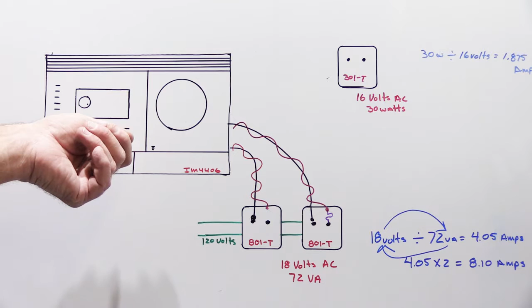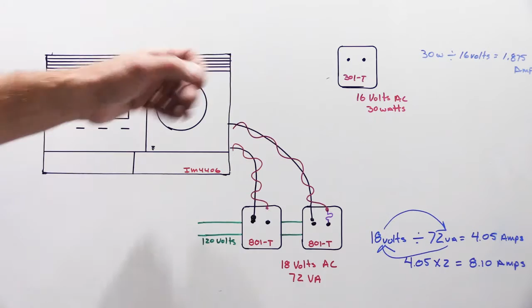So a 301T is a really good choice for a testing transformer because it's very close in the volts, which is important for the electronics in the master station. The watts are undersized. It doesn't really have enough power to run it fully and properly. But on the other hand, when you're testing a master station, you're not cranking it up to party level. You're just running it at a low level to see what does and doesn't work. So for a few minutes, this is just fine.